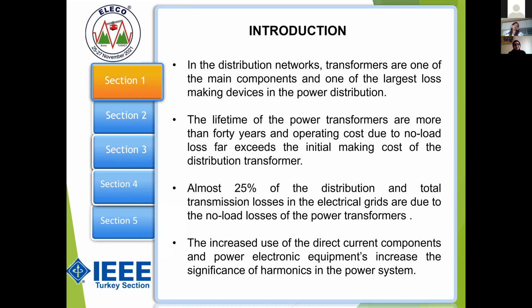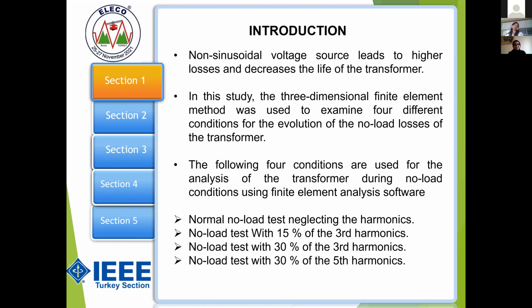And we all know that in the last few decades, the use of direct current components and other power electronic equipment has been increasing significantly, and they are creating harmonics in the power system. Non-sinusoidal voltage sources lead to higher losses and decrease the life of the transformer, because higher losses mean higher temperature of the transformer. So in this study, we made a 3-dimensional model of the transformer to evaluate 4 different conditions for the no-load losses. These are the 4 conditions given below.